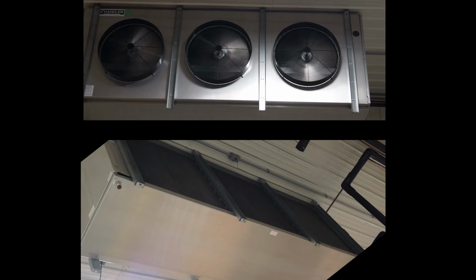This is a view of the front and back side of a cooling unit. This cooling unit looks to be satisfactorily clean, showing no visible dust or condensation. This is a satisfactory finding in a critical area. Here is another shot of a cooling unit that has been in operation for some time.